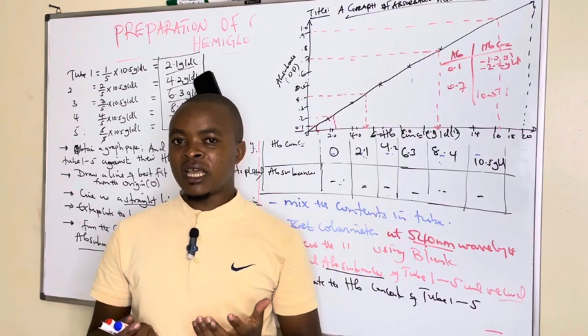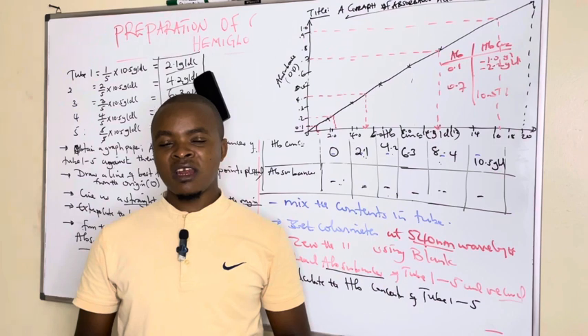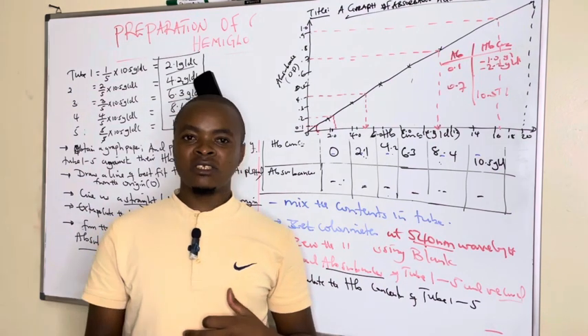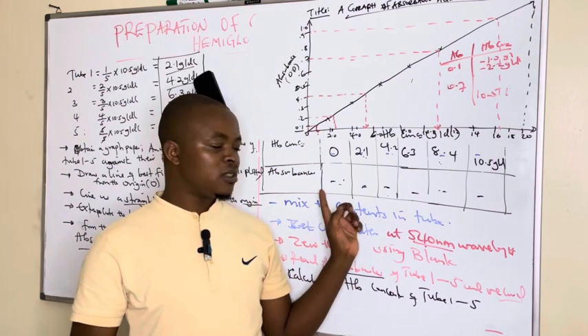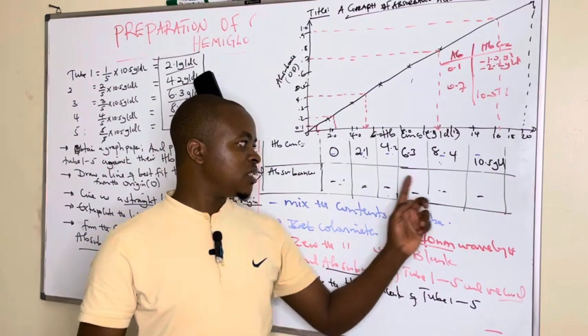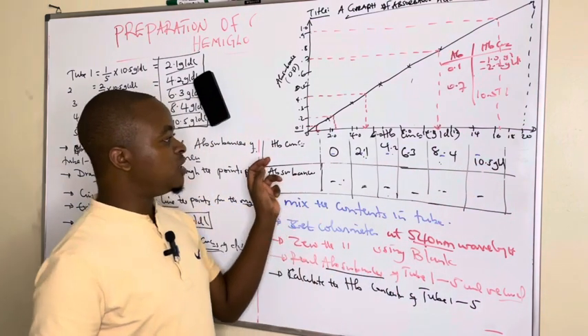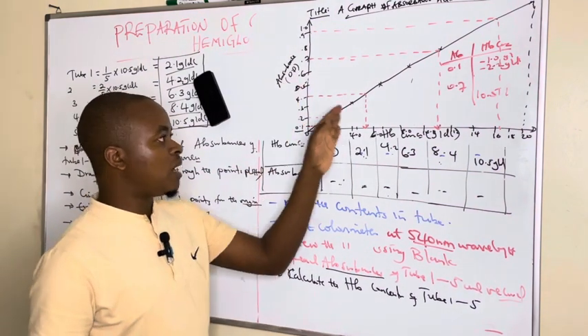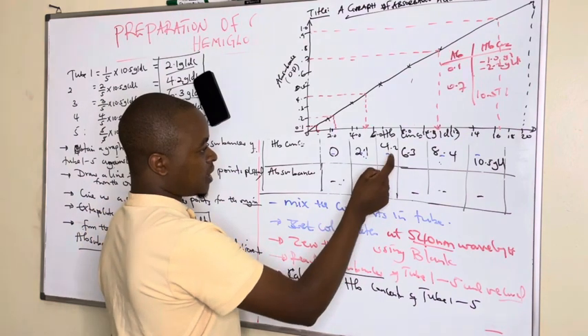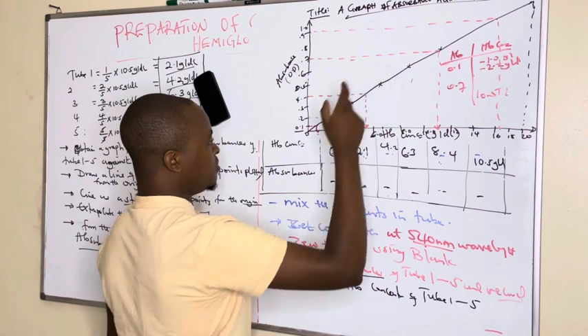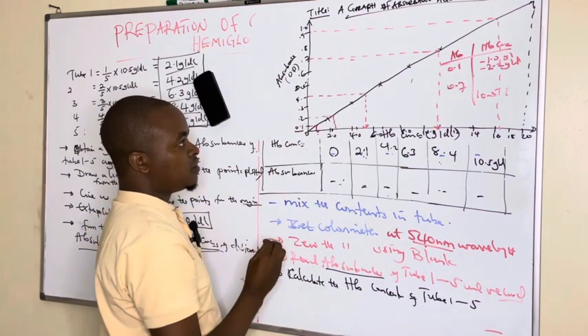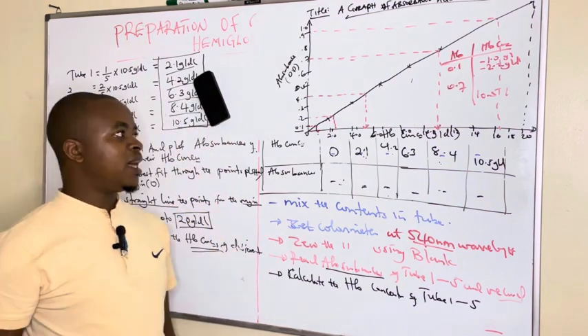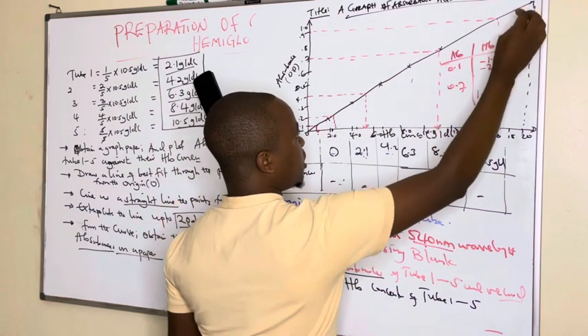Then we set the colorimeter at 540 and zero it. You read the absorbances of each tube from tube 1 to 5, then record them in the table. Then you calculate the different concentrations of HB after making serial dilutions. You then plot HB concentration against their absorbances to come up with the calibration curve. You draw a straight line from the origin, and if you have not made many errors, it should be a straight line, which is extrapolated up to 20.